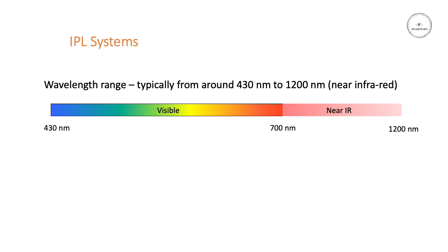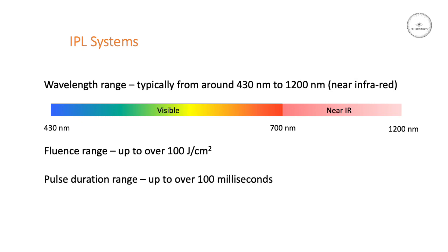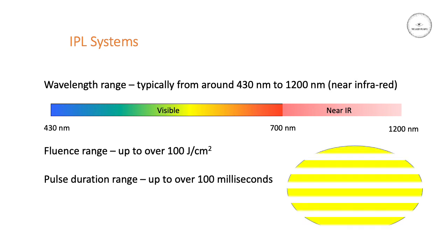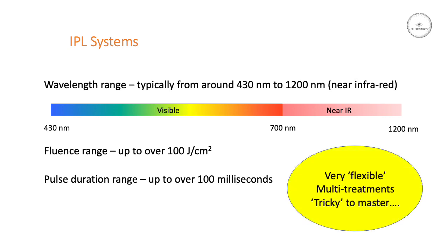This means it contains both visible and invisible infrared light. The fluence range can be up to over 100 joules per square centimeter, while the pulse duration range can go over 100 milliseconds. This is mostly due to the fact that most IPL systems generate a train of sub-pulses and add them all together into one single pulse. This makes IPL systems very flexible since you have quite a choice over wavelength, fluence and pulse duration, which means it can also treat a number of conditions in the skin.